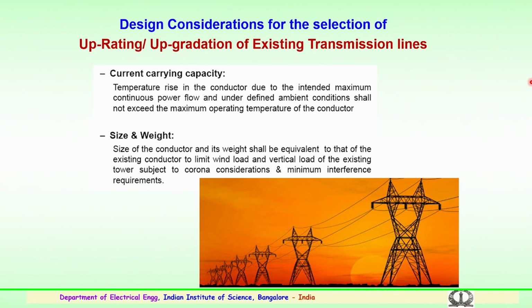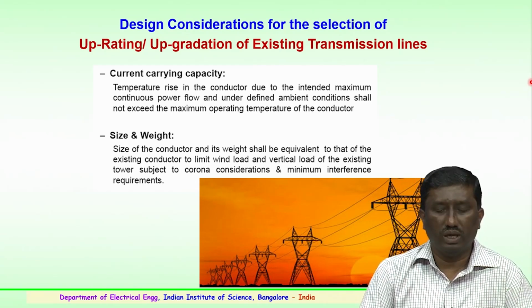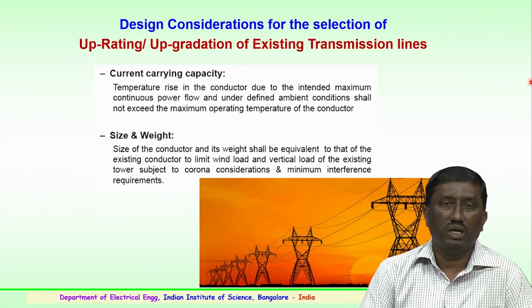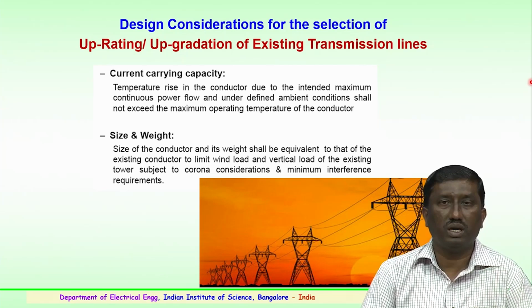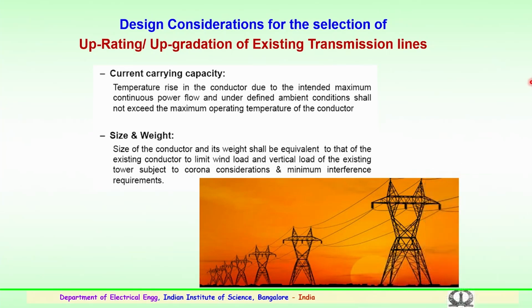So, we will discuss some of the design considerations, particularly for the selection and upgradation of the existing lines: how the conductors, while replacing, could be advantageous, and what the necessary design aspects to be followed are. For the current carrying capability, we know that the temperature rise in a conductor is due to the intended maximum continuous power flow under defined ambient conditions. This should not exceed the maximum operating temperature of the conductor. In the case of high temperature conductors, typically between 150 to 200 degrees is the current carrying capability. Thermal rise could happen, and the size and weight of the conductor should also be equivalent to that of the existing ACSR conductor.